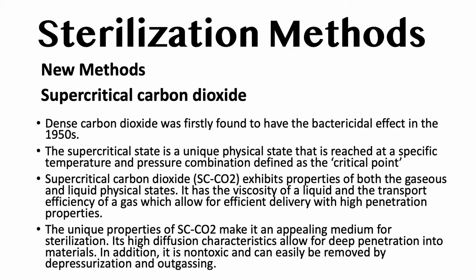There is a new method in sterilization, supercritical carbon dioxide. Dense carbon dioxide was first found to have a bactericidal effect in the 1950s. The supercritical state is a unique physical state that is reached at a specific temperature and pressure combination defined as the critical point. Supercritical carbon dioxide exhibits properties of both gaseous and liquid physical states. It has the viscosity of a liquid and the transport efficiency of a gas, which allows for efficient delivery with high penetration properties.